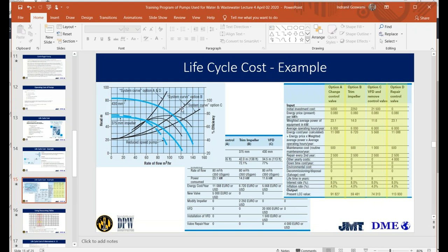And so the A and D, B and C options are less throttled, so there is less resistance to the flow within the pump itself. And so we have to generate these system curves, and therefore from that look at the intersections of that curve and whichever impeller we are using. So that's the background work that must be done in order to determine what the characteristics of the different options are.